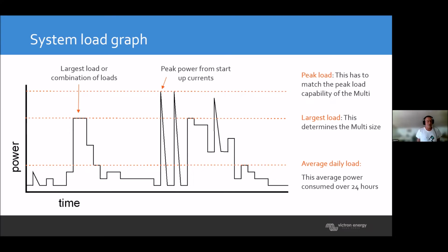Most of the time, consumption in the system is very low, but in the morning and evening you always have some peak loads. It's important that normal loads can be supplied directly from the inverter, and you only have peaks from small starts that's bigger than what the inverter is doing continuously.